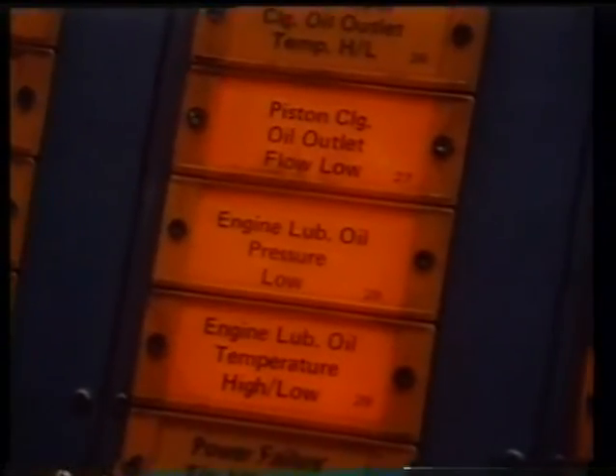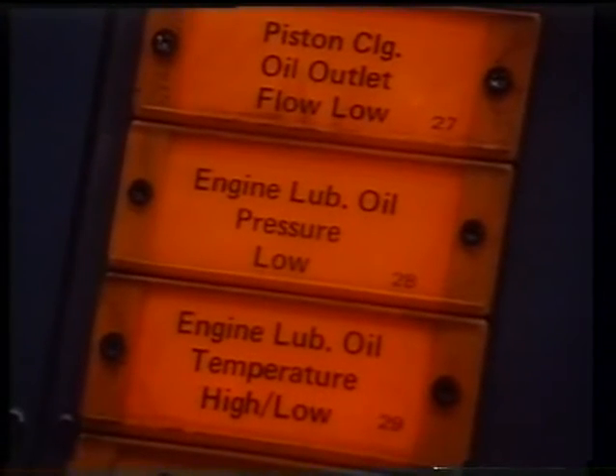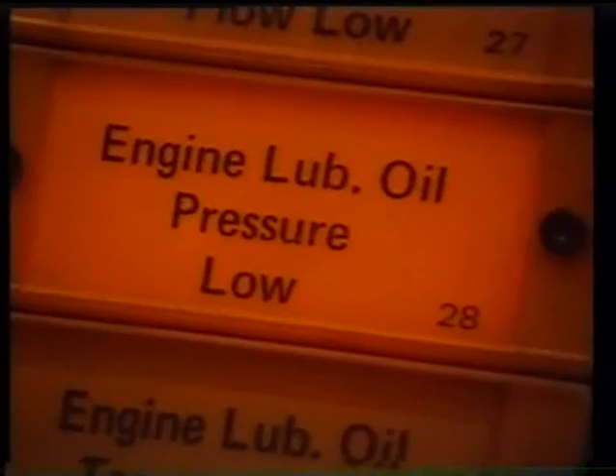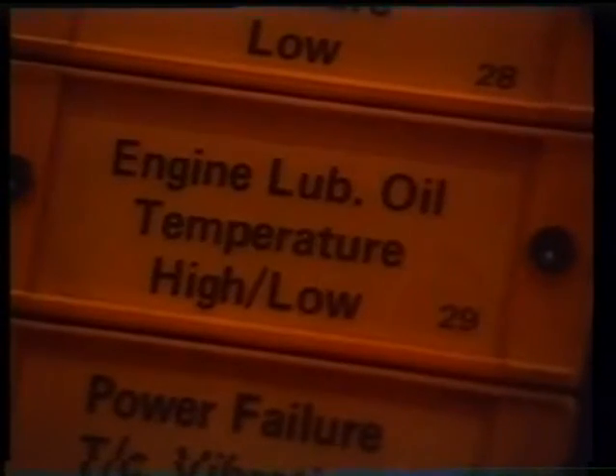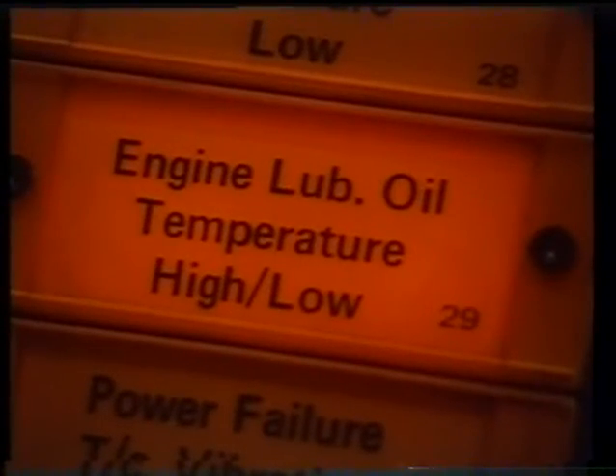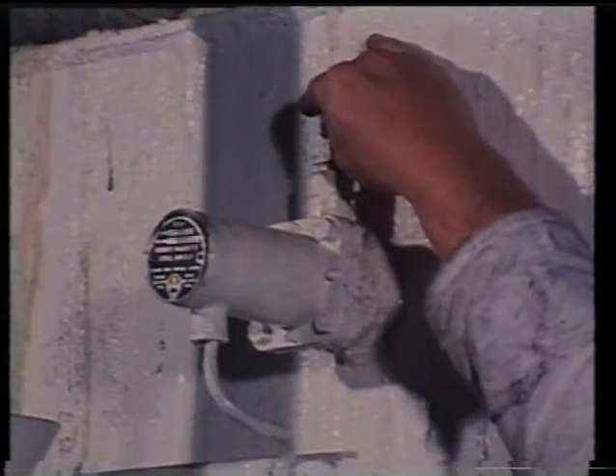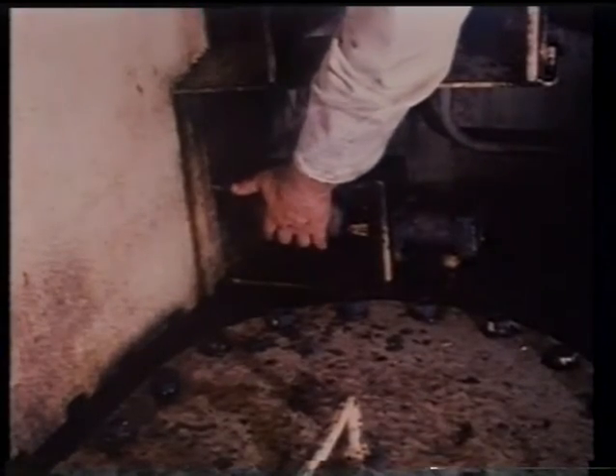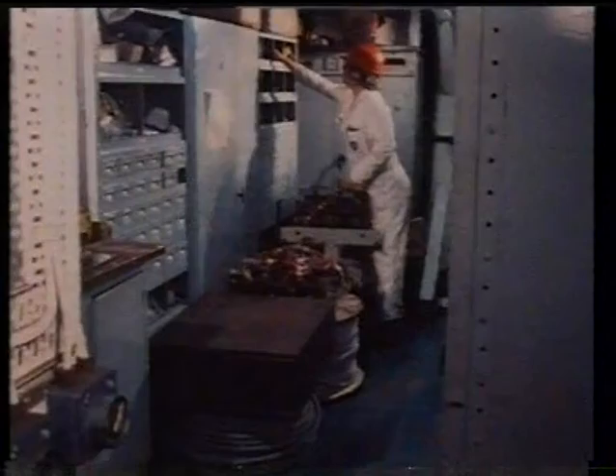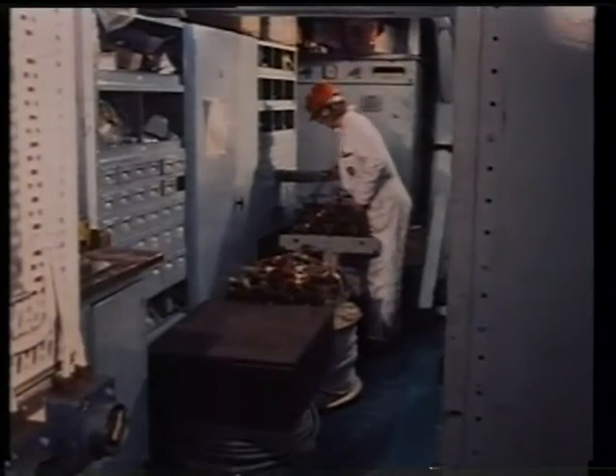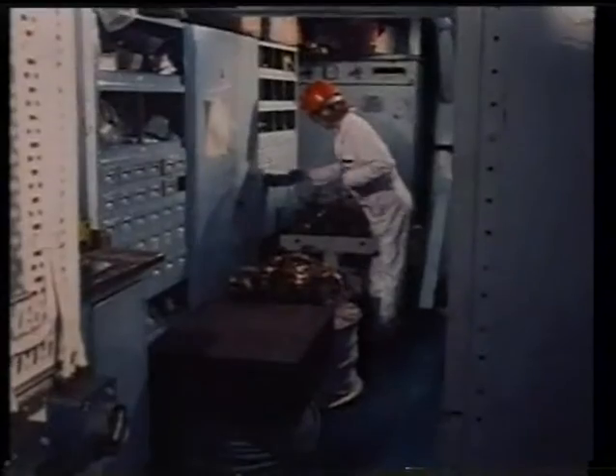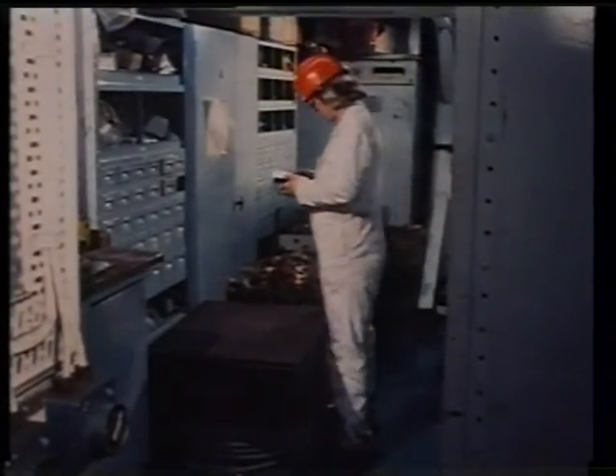If your ship is classified for unattended machinery space, the so-called UMS operation, the electrical survey will be extended to include all alarms, fire detection controls and fail-safe installations. All alarms associated with the main engine, auxiliary machines, lubrication and cooling are to be tested for correct function by operating the sensor switches by hand or simulating the switch action under the expected alarm conditions. The duplicate bilge level alarms must be proved to work to the satisfaction of the surveyor. Check that all required electrical spares are available for inspection in the electrical spares store. They must be correctly stored and in good condition.